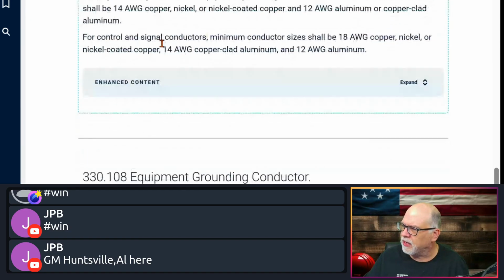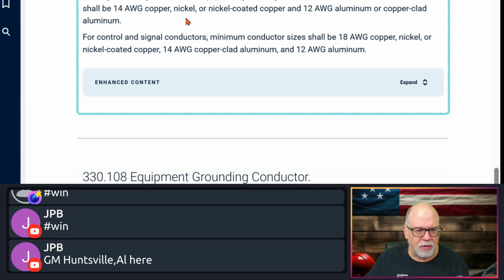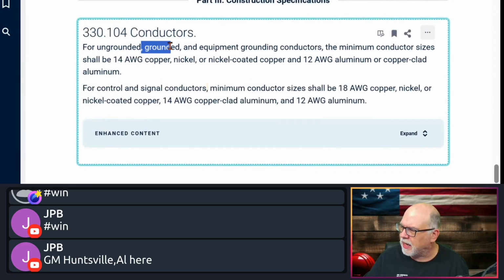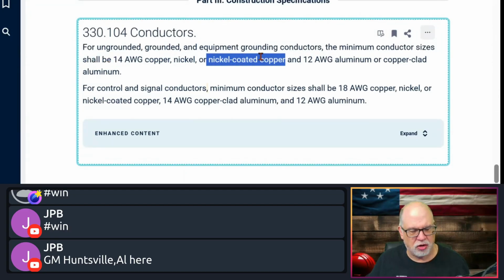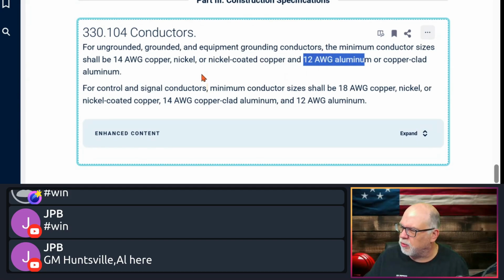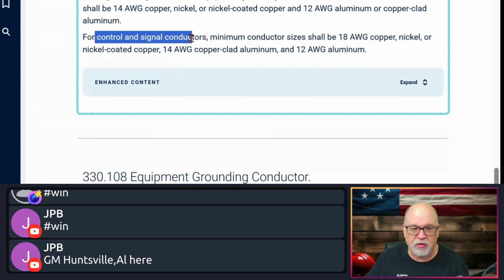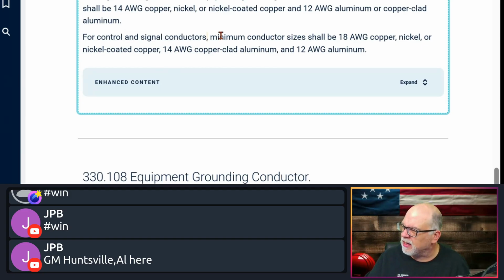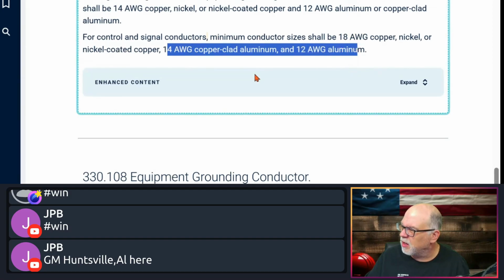The conductors, it makes it very clear. The conductors, it can be an MC cable. It says it can be the ungrounded, grounding, and equipment grounding conductors. The minimum conductor size is 14 copper, nickel, or nickel-coated copper. Have not seen those in years, okay? And 12 aluminum or 12 copper-clad aluminum. It says the control circuit conductors. This is how we can get away with the MCPCS, for example, which is done for power and remote control. It says for control and signaling, the minimum conductor size is 18 gauge copper or 14 gauge copper-clad aluminum or 12 gauge aluminum, okay?